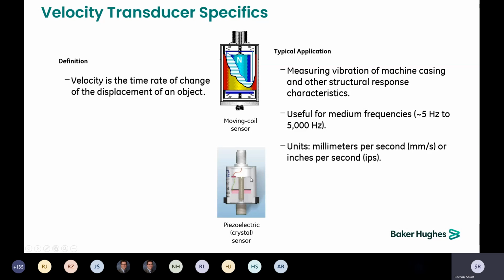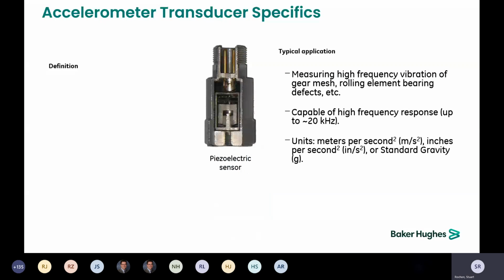The piezoelectric style consists of a reference mass, a preload bolt, a piezoelectric crystal, and a charge circuit to pre-charge the piezoelectric crystal. And as the machine moves, the inertia of that reference mass compresses and relieves the pressure on the piezoelectric crystal, causing it to give an electrical signal that we then convert into inches per second. Accelerometers are basically the same thing, just without the integration circuit. Here you can see the reference mass. The piezoelectric crystal is actually up here in the top.